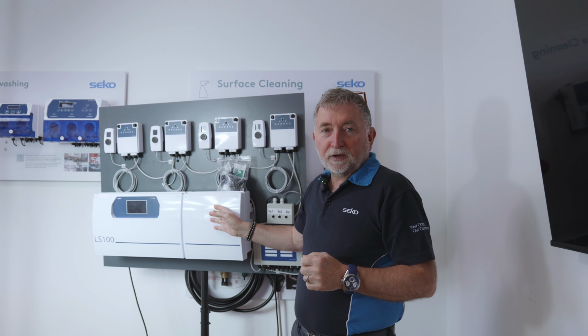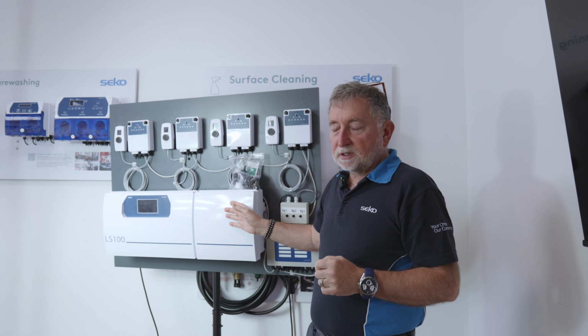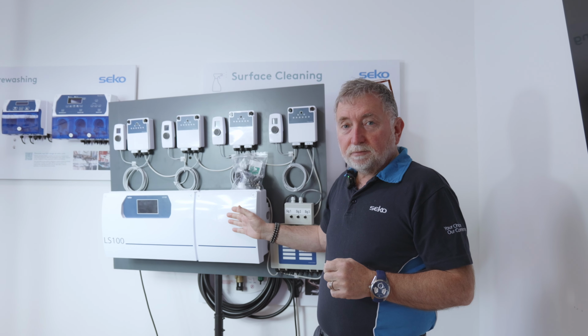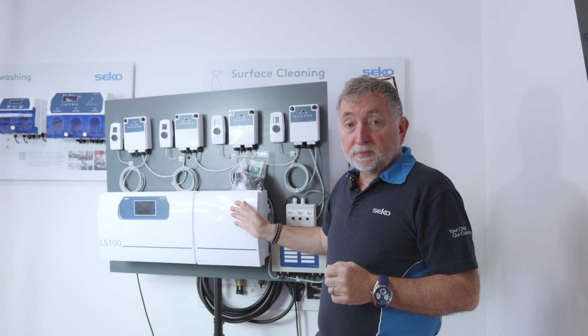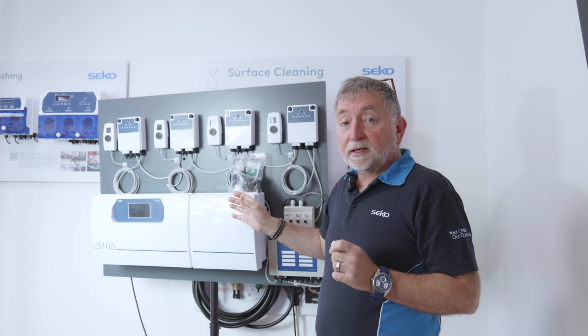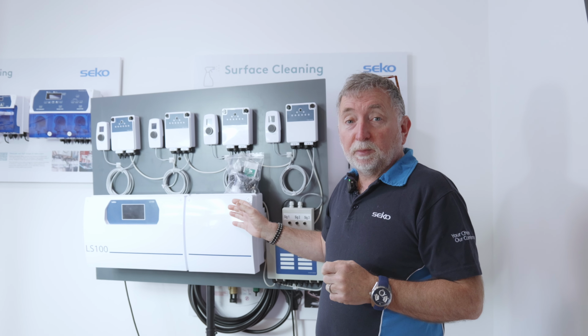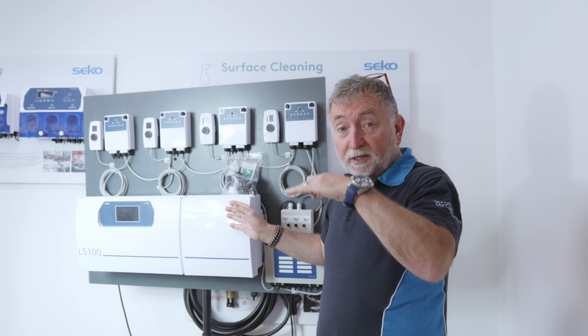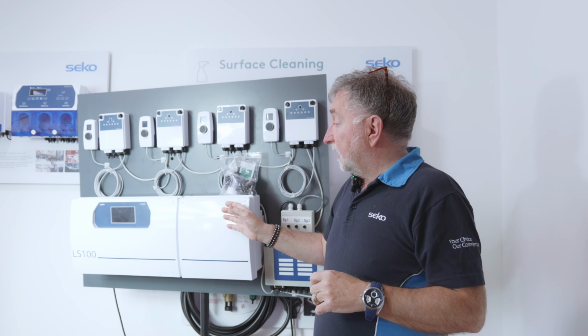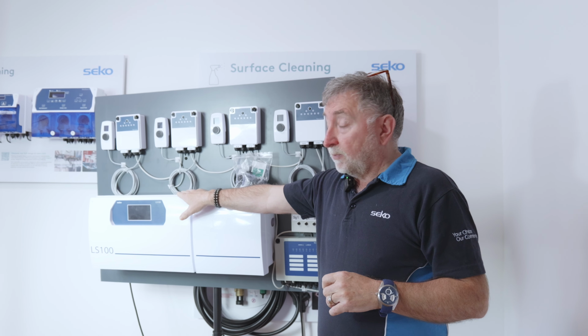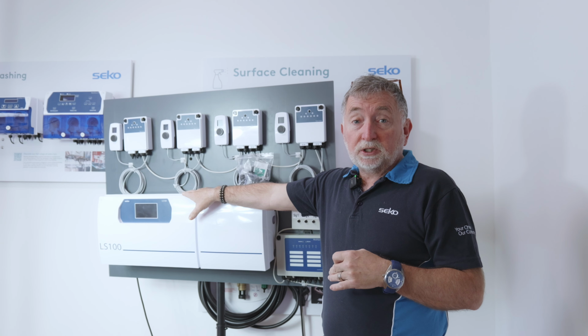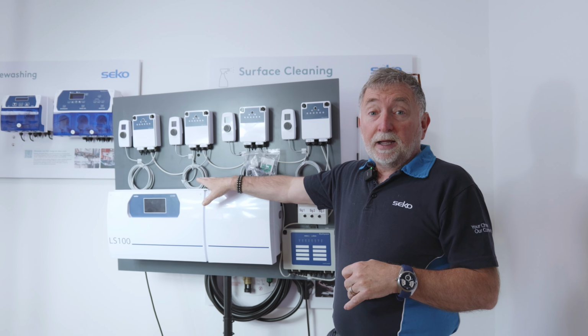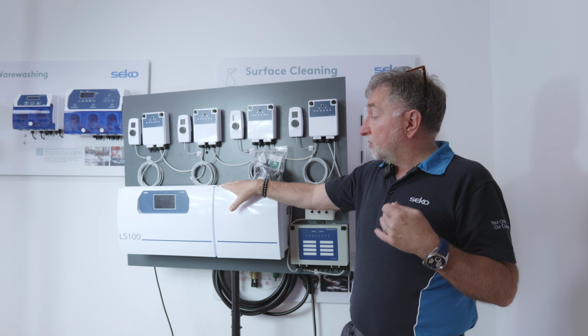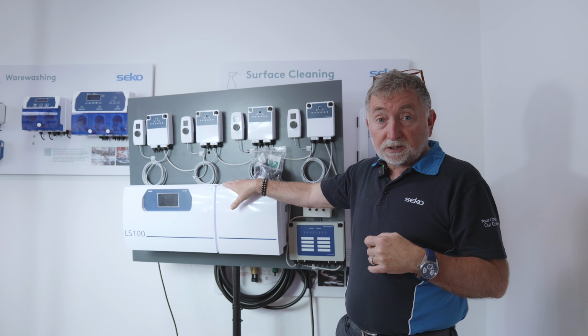In this video we're going to be looking at SEKO's LS100 Venturi dosing system for laundries. Being a Venturi system, it has no actual chemical dosing pumps. It's water driven, so that is something to bear in mind because you will need a minimum pressure of 1.5 bar for the chemical activation to take place. Now the laundry system can pump up to 10 chemicals with the addition of an additional box, and it can actually supply 4 different washer extractors.